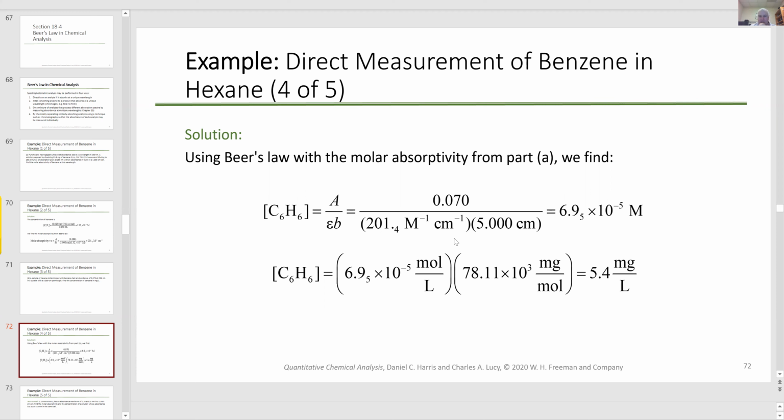For example, here we have a 5 centimeter path length, that's a pretty weird cuvette. Can we change our cuvette? Yes, exactly. We just go to a thinner cuvette, and we measure blank and sample with that new cuvette. So going down in absorbance is not that hard usually. Either dilute or use a thinner sample. Excellent. Cool.